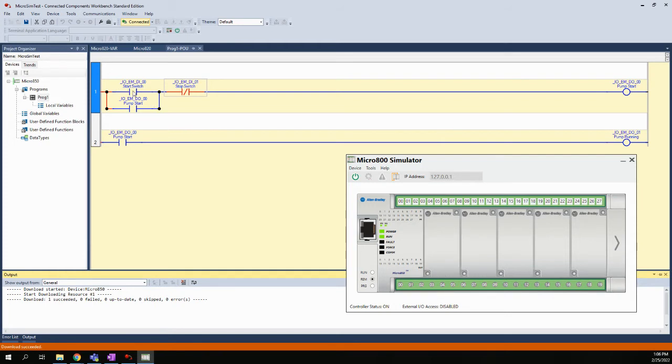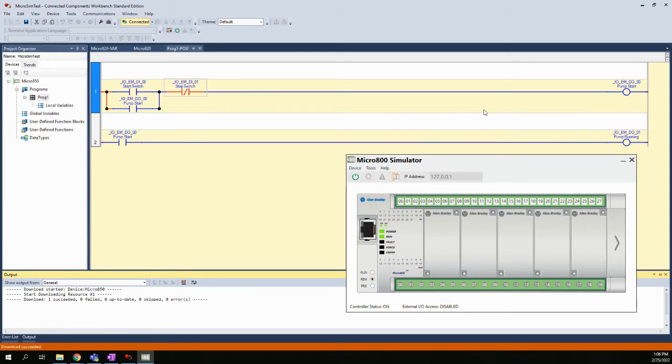Here's the logic: I have my start switch and my stop switch and my pump start. Then I have my pump start working as the latch. I also have a contact from the pump start here that will turn on the pump running indicator.